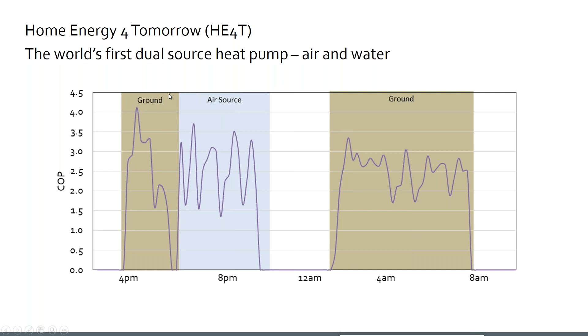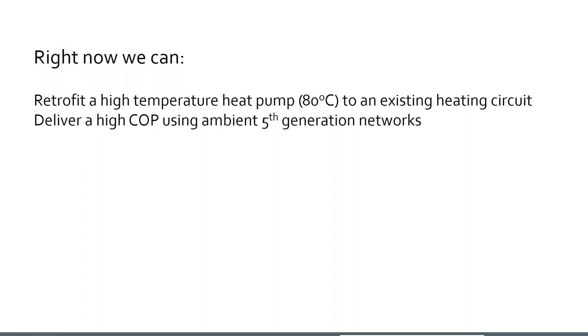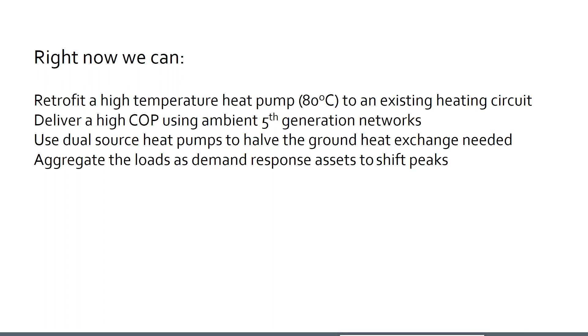So to sum up those projects, right now I think it's important to highlight a few features: you can retrofit a high temperature heat pump into an existing heating circuit, you can deliver a good COP and improve that over time, you can create a dual source heat pump that lets you reduce the size of the ground heat exchange you need, and you can use demand response control systems to aggregate loads across your network and shift peaks. And then to reduce costs, which is what we're exploring right now, is flexing tariffs and using DSR revenue and other options, well, RHI while it's still there, to reduce the cost.